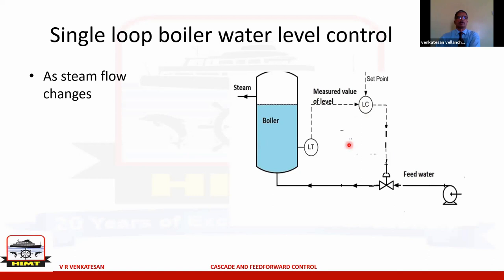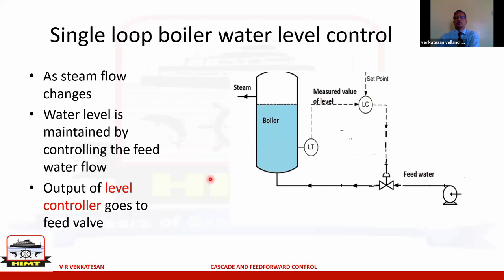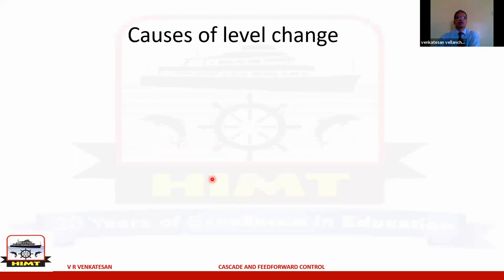The way this works: if steam flow increases, the water level will fall. The drop in water level is detected, compared against the set point, a deviation is produced, and the feed valve is opened or closed accordingly. The output of the level controller goes to the feed valve. This is a simple and very commonly used application, but it has some drawbacks.